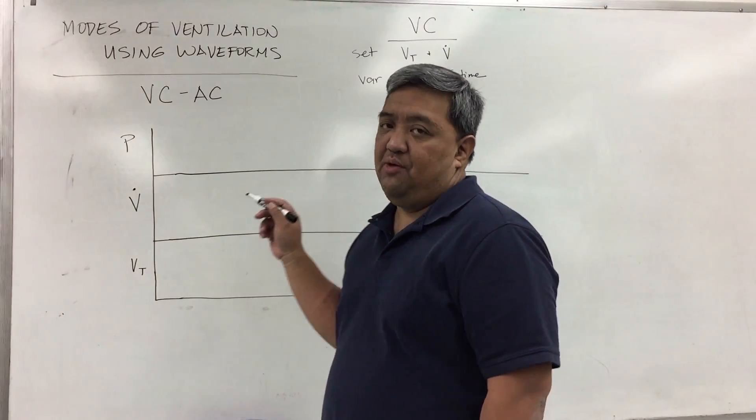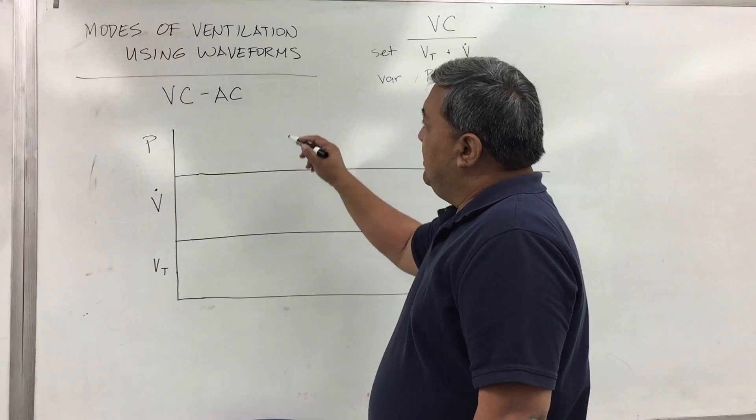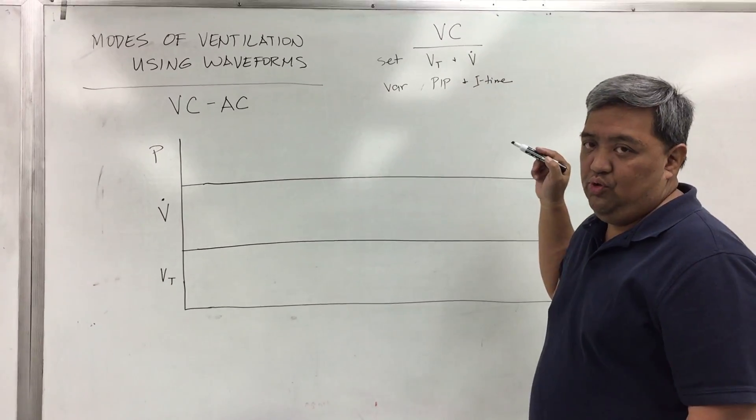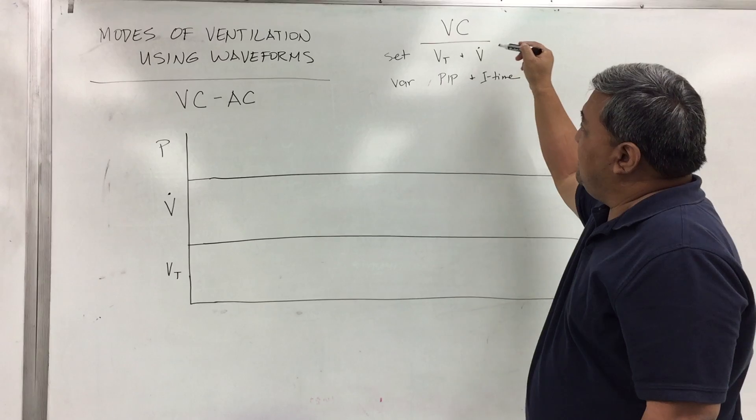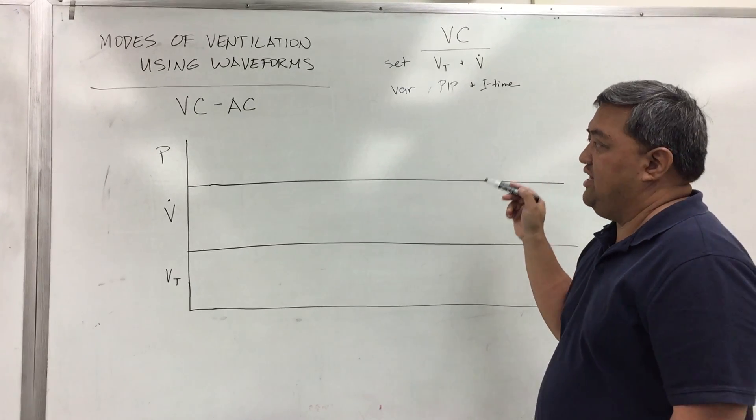The next mode that we're going to talk about is volume control in the assist control mode. In volume control, again based on our controllers earlier, set is tidal volume and flow and variable is peak inspiratory pressure and your I-time.